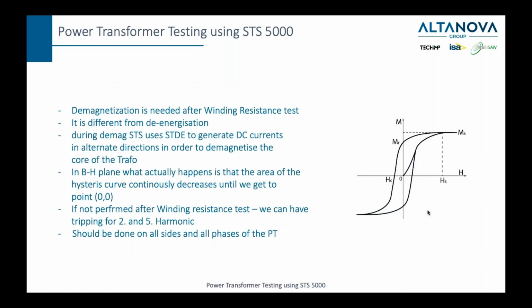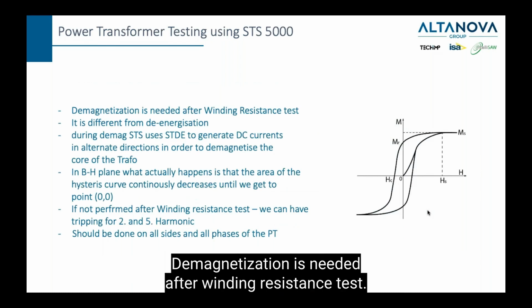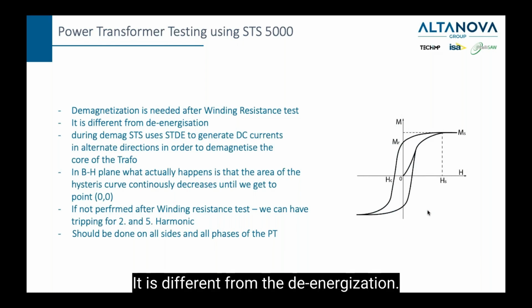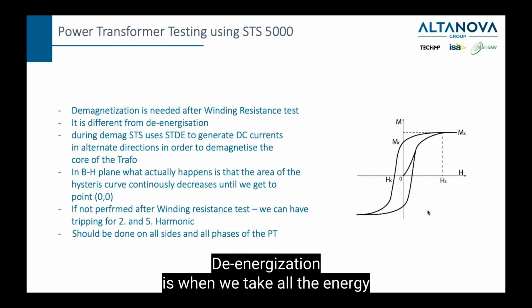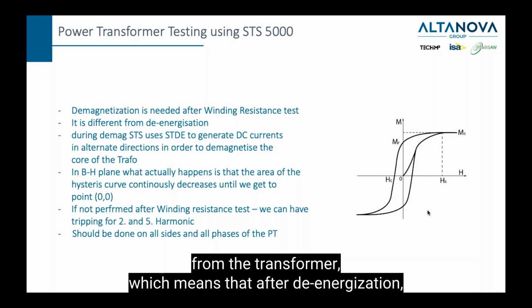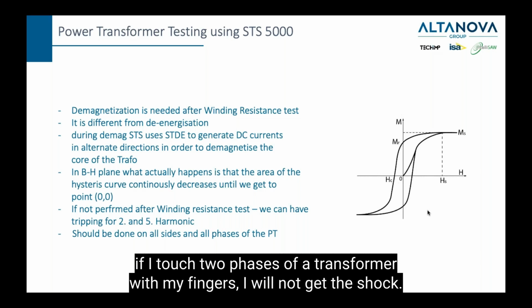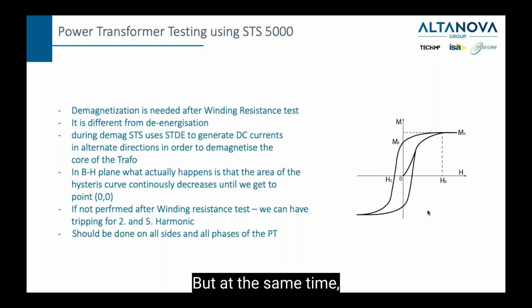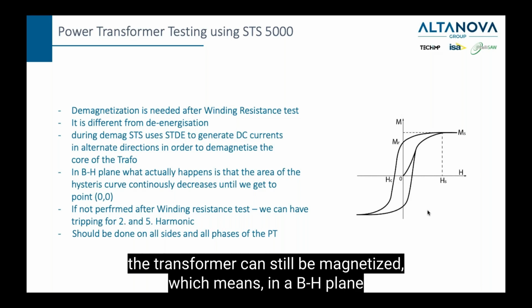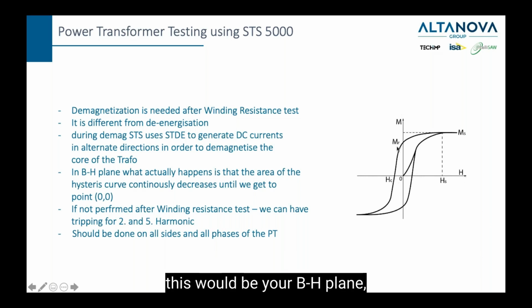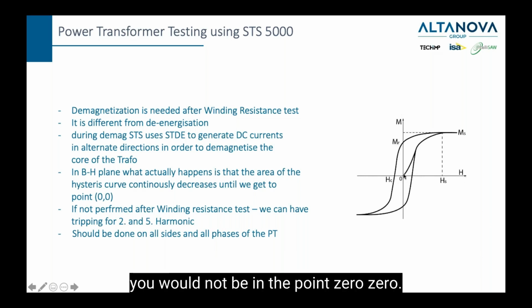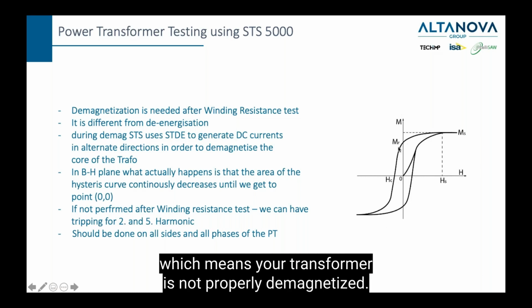Demagnetizing is not a test. Demagnetization is needed after a winding resistance test. It is different from de-energization. De-energization is when we take all the energy from the transformer, which means that after de-energization, if I touch two phases of a transformer with my fingers, I will not get a shock. But at the same time, the transformer can still be magnetized, which means in a BH plane, you would not be at the point 0,0. You would be somewhere else, which means your transformer is not properly demagnetized.